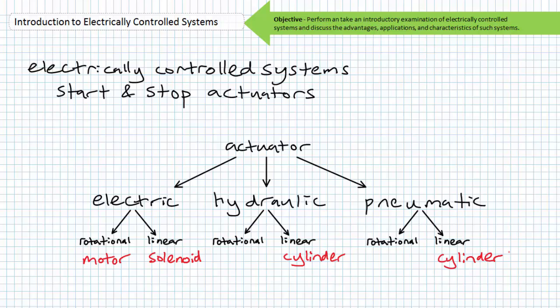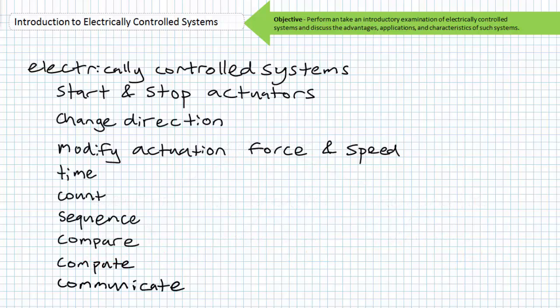Numerous examples of actuators exist, and despite their differences of input energy or form of mechanical movement, they can all be electrically controlled. A magnetic contactor can start or stop a motor, and a solenoid-operated directional control valve can stop or start a hydraulic cylinder. In addition to starting and stopping actuators, electrically controlled systems can change direction and modify operating characteristics of actuators, such as varying the rotational speed and torque of an electric motor and varying the extension or retraction force or speed of a hydraulic cylinder.